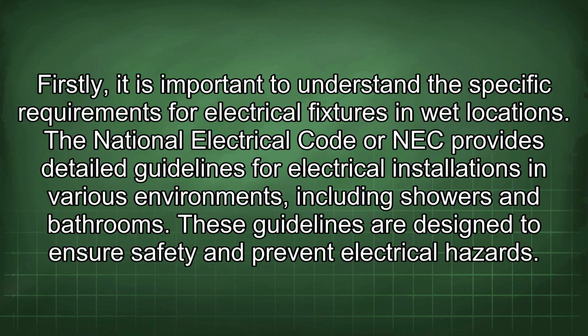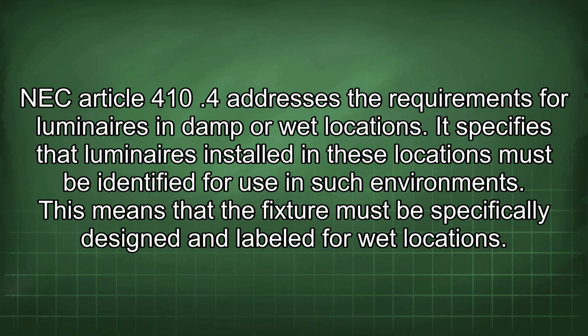Firstly, it is important to understand the specific requirements for electrical fixtures in wet locations. The National Electrical Code, or NEC, provides detailed guidelines for electrical installations in various environments, including showers and bathrooms. These guidelines are designed to ensure safety and prevent electrical hazards. NEC Article 410.4 addresses the requirements for luminaires in damp or wet locations. It specifies that luminaires installed in these locations must be identified for use in such environments. This means that the fixture must be specifically designed and labeled for wet locations.